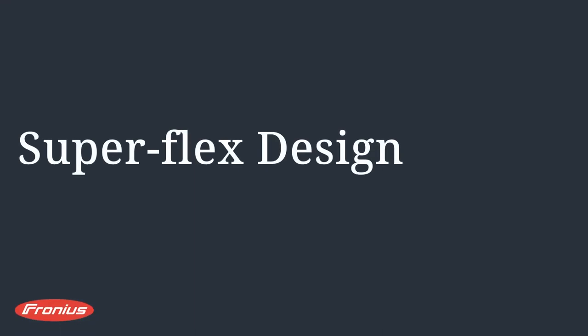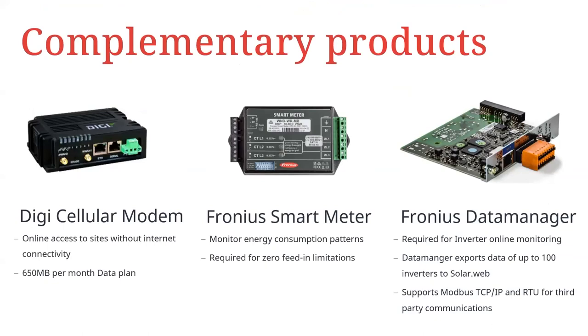A question came in: how does one data manager collect information from 100 inverters on a site? The inverters can be daisy-chained together to create an information path called the solar net loop. All data collected from each inverter is exported to the master inverter with the data manager card installed. From that data manager card, all packets of information go to the Solarweb servers back in Austria at Fronius headquarters. From Solarweb, you'll be able to access all of the site's information as well.